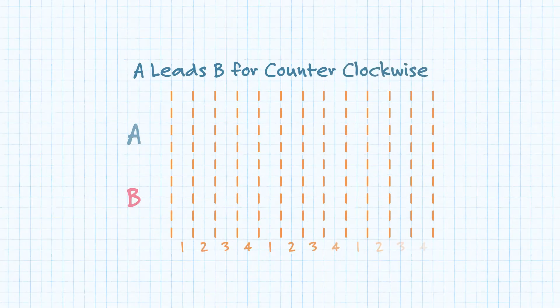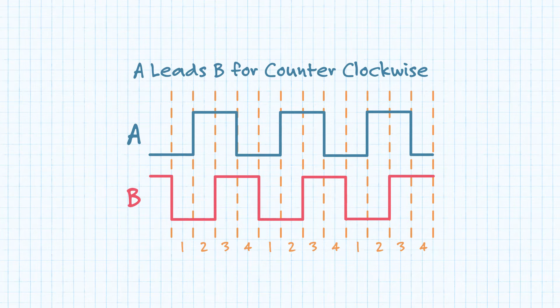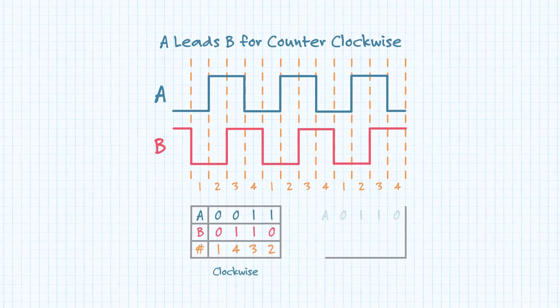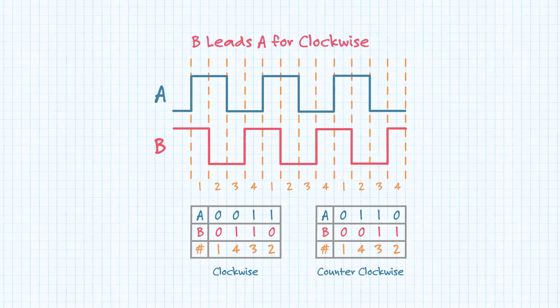With an incremental encoder, the output typically has two square waves on individual channels that are output 90 degrees out of phase of each other. With the two square waves offset by 90 degrees, as the encoder rotates, it is possible to calculate which direction the shaft is moving by looking at the order of the incoming signal state changes.